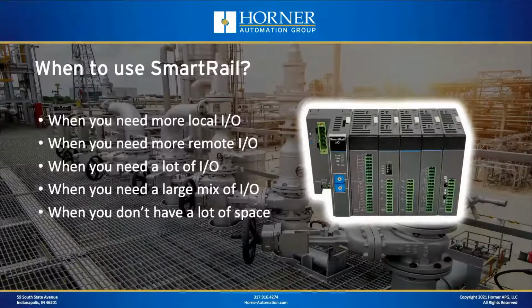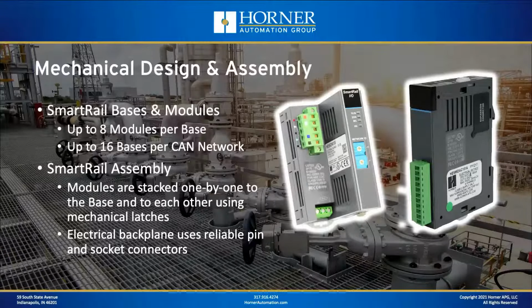All right, let's start with the mechanical design and the assembly of the product. So SmartRail comes in effectively two pieces, or with two main components, bases and modules. You can have up to 8 modules per base, and then you can have up to 16 bases per network. So think about that. If you've got 16-point digital modules, and you've got 8 of them connected to a single base, that's a lot of I/O, and you could have up to 16 of those bases. So you can really add the I/O quickly if you had a dense system.